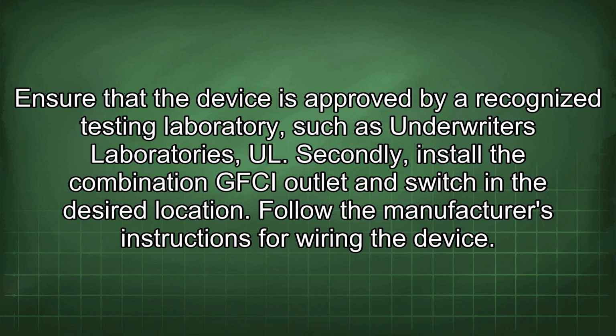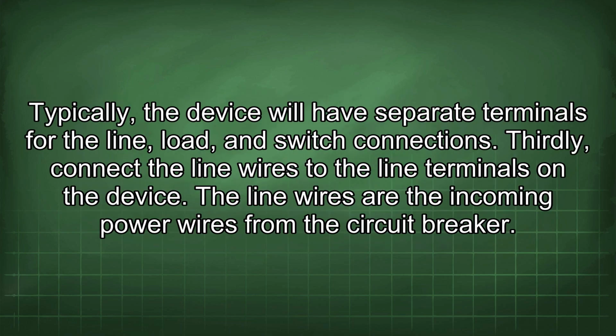Secondly, install the combination GFCI outlet and switch in the desired location. Follow the manufacturer's instructions for wiring the device. Typically, the device will have separate terminals for the line, load, and switch connections. Thirdly, connect the line wires to the line terminals on the device. The line wires are the incoming power wires from the circuit breaker.